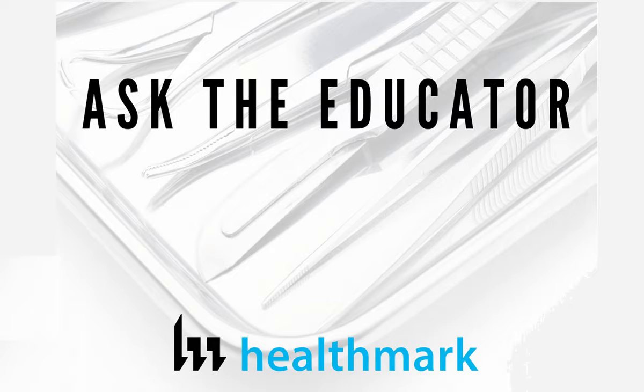And it's become very clear that endoscopes in storage are still wet. Anyone that's removed an endoscope from an AER knows that it's still dripping. You hold it vertically and water drips out the distal tip. The outside of the scope is still wet. And the focus is shifting to active drying of the endoscope. So similar to everything else, they're going to be paying attention to what the manufacturer says to do as far as drying of the endoscope. And then if you're using any automated processes, they're going to see that those match and you're following those steps appropriately.